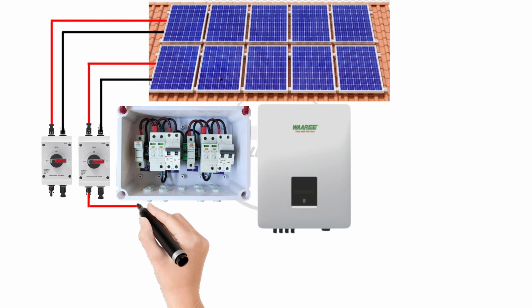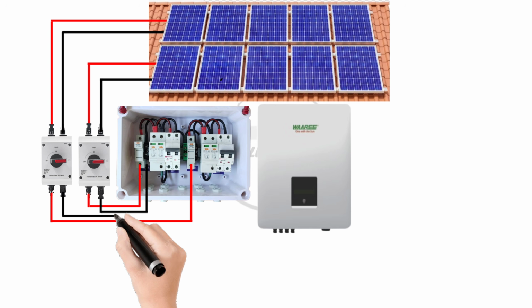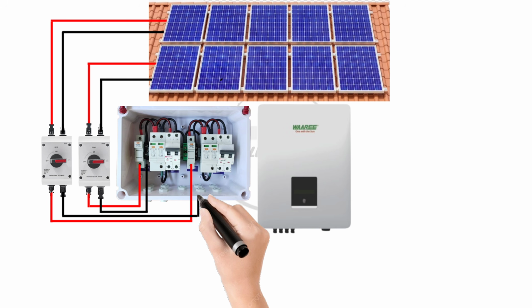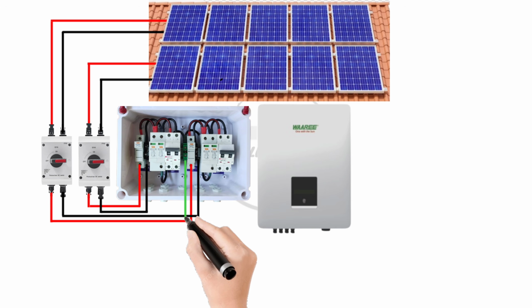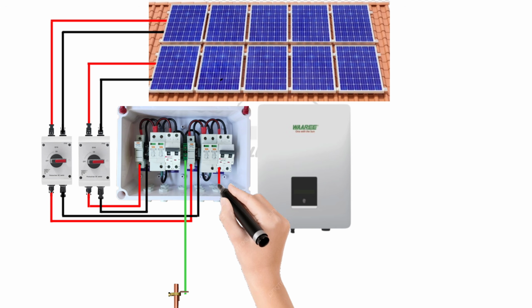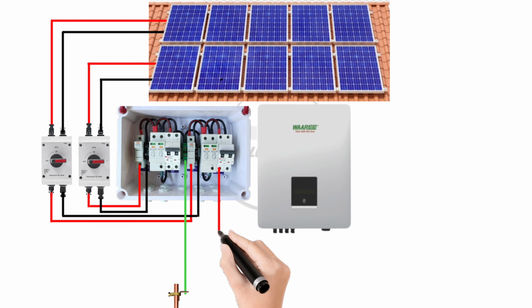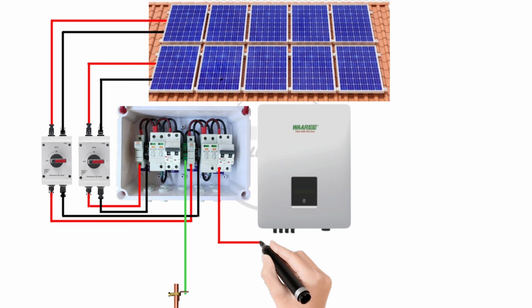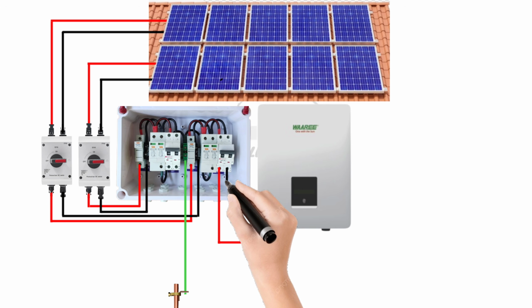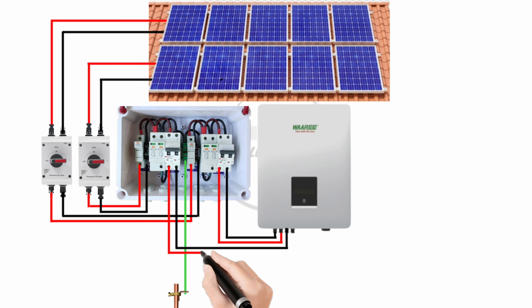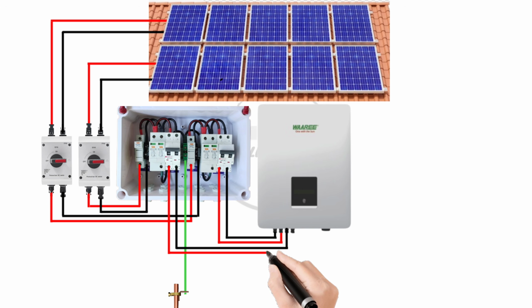Connect the positive output of the isolator switch to the positive input of the DC MCB. Earth connection. Connect the earth terminal of the SPD to the ground. Connect the positive output of the MCB to the positive PV input of the solar inverter. Connect the negative output of the MCB to the negative input. Important considerations. DC systems are polarity sensitive. It's crucial to connect the positive and negative wires correctly. Reverse polarity can damage equipment. Always double check all connections.